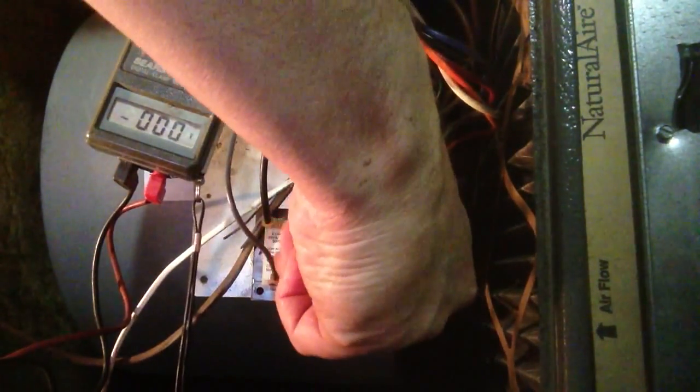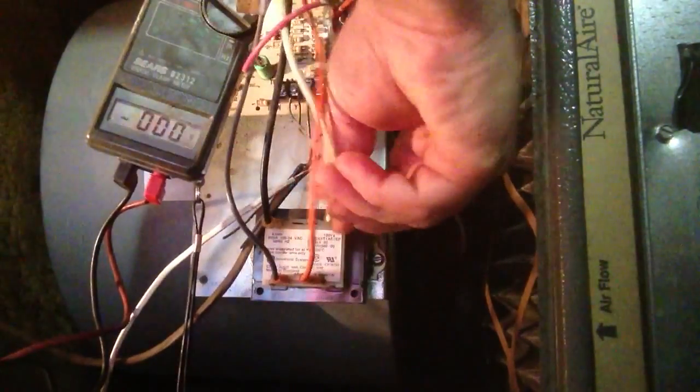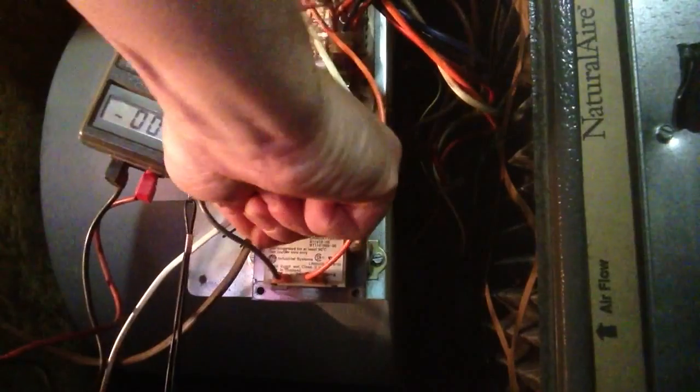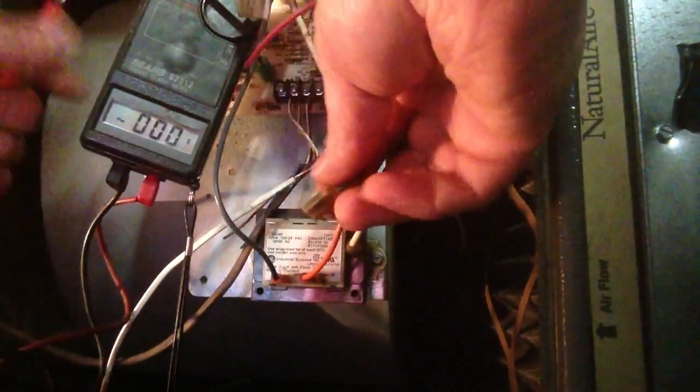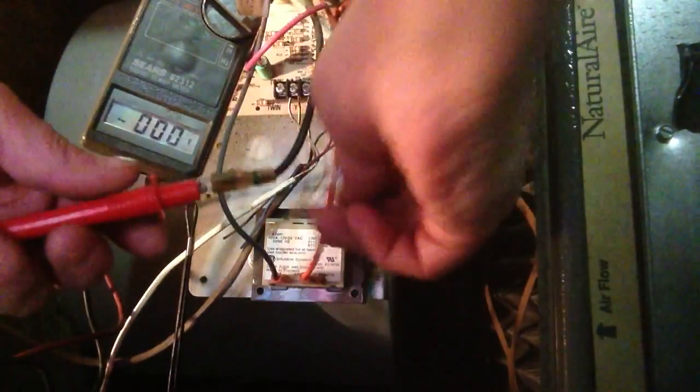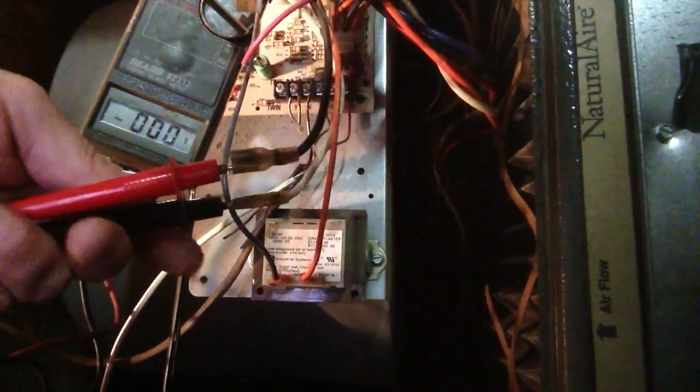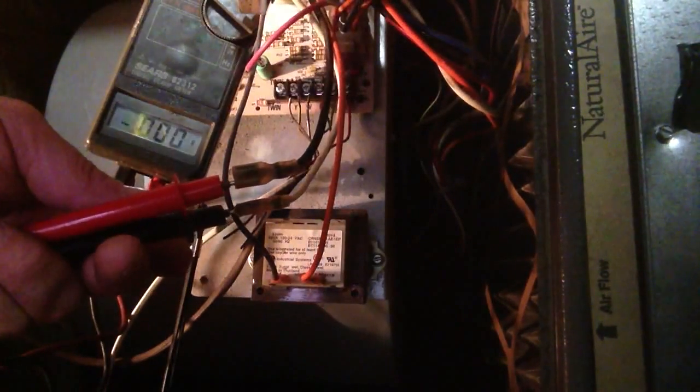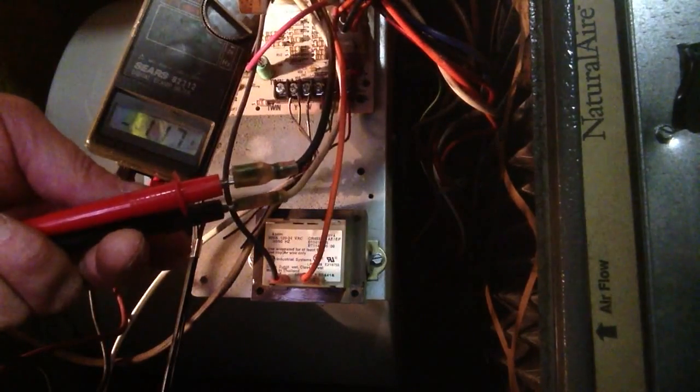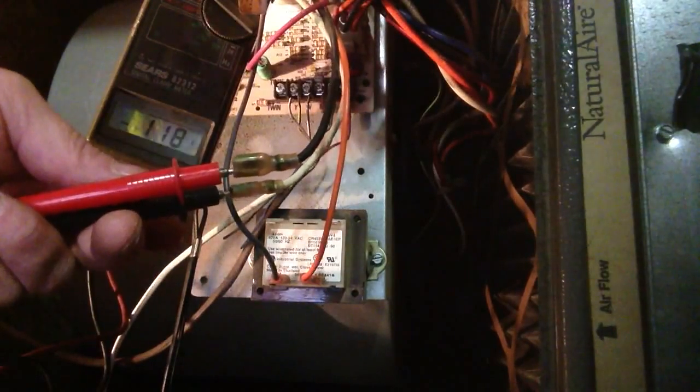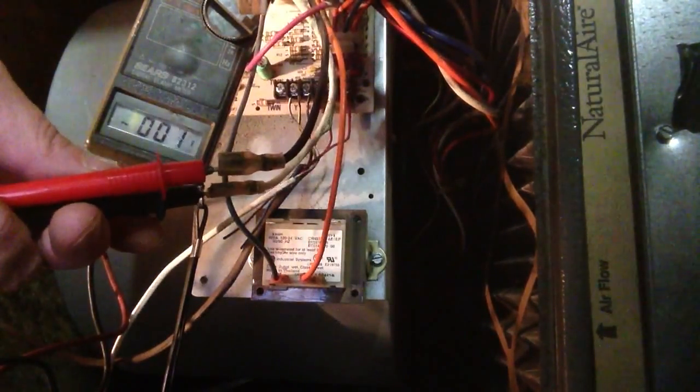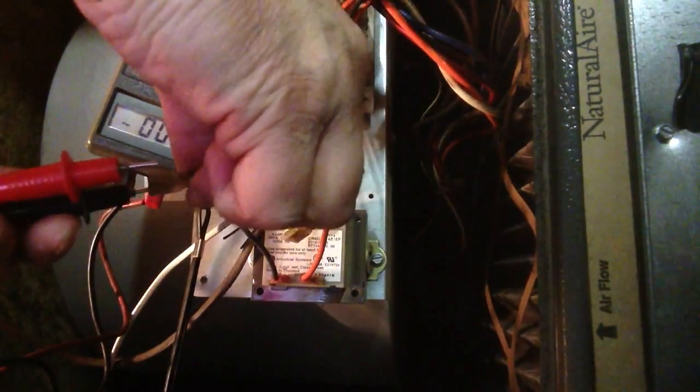Now, if you don't get voltage there, you want to make sure you have voltage going into the transformer. And we can see that we have 117 volts. So we have voltage going in, we have voltage coming out, we know our transformer is good.